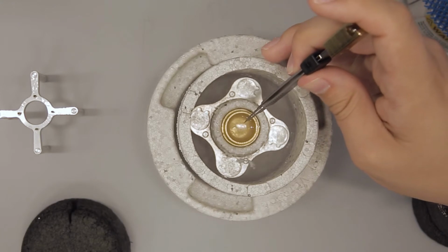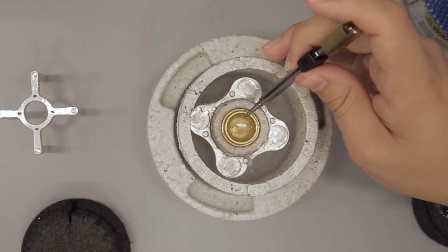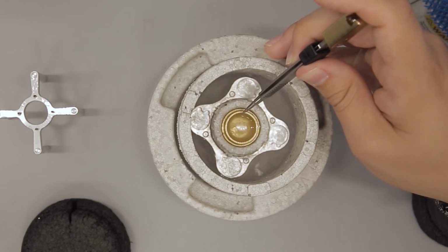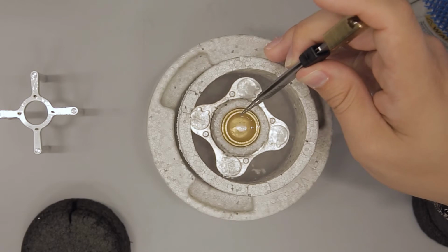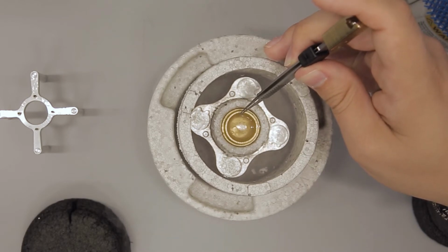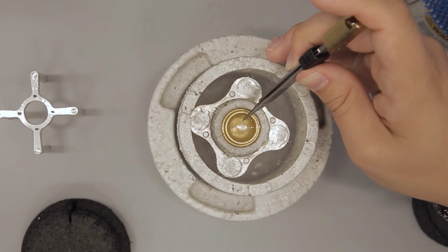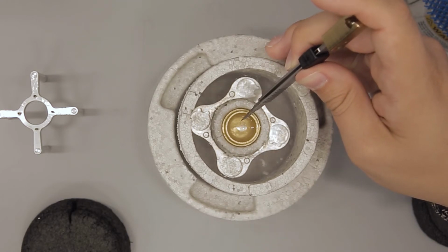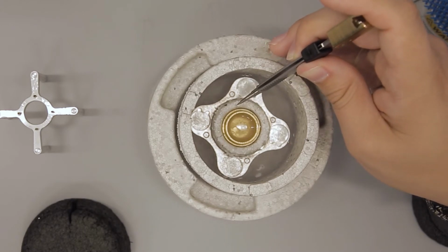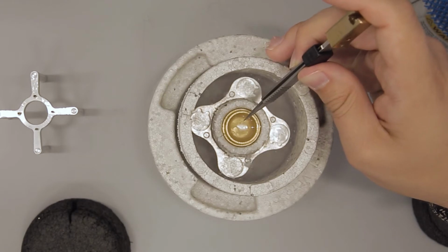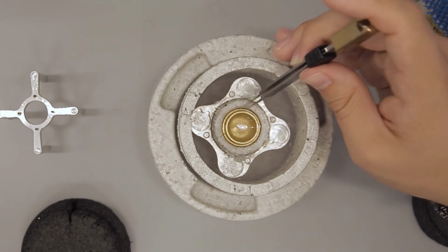Also, that can be attached to your grid, and when you use a side entry holder, when you insert the holder in the microscope with the airlock, in most cases not all of that ethane is evaporated away, and you will still see that. When you have an autoloader based system, when you load a sample, the turbo pump will pump the autoloader, and that actually will cause the ethane to sublimate. So the solid ethane for autoloader based systems is not anymore a source of serious contamination.